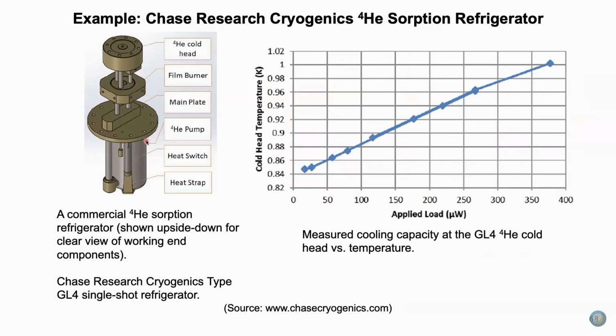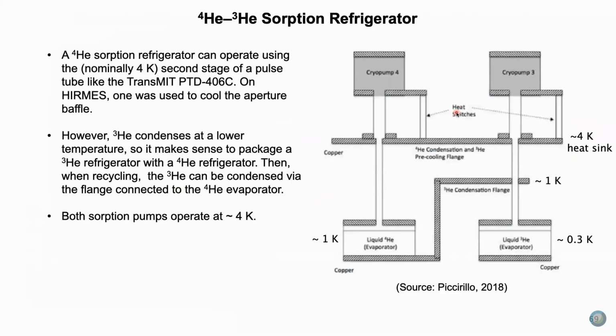Here's another example, and this is a commercial one built by Chase Research Cryogenics, a helium-4 sorption refrigerator. This is shown upside down. The sorption pump is on the bottom in this drawing. And then you've got the helium-4 cold head. It's a very simple, compact unit and very reliable. These, by the way, are the sorption refrigerators that were used for Hawk Plus and HIRMES, or Chase Research sorption refrigerators. And there's a nice cooling curve for the cold head.